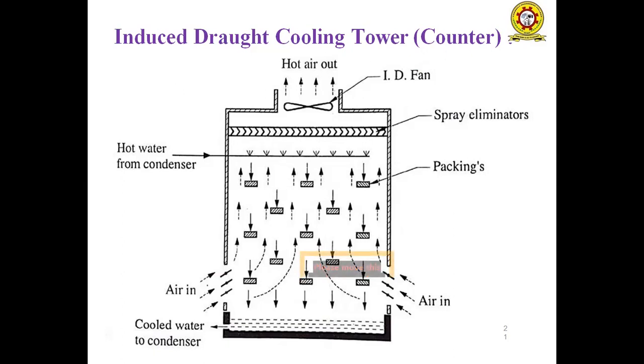In this induced draught cooling system, it is a mechanical draught tower with a fan. The induced fan is situated at the top, which pulls the air through the tower. So this fan induces the hot moist air from the discharge. This produces a lower entering air velocity and a high discharge air velocity, which reduces the possibility of recirculation in which discharged air flows back into the intake. The fan or fin arrangements are known as draw-throughs.